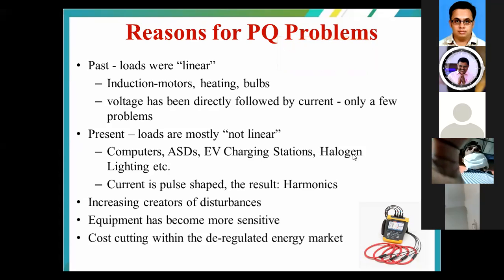That means in the sinusoidal wave, we are going to switch on or switch off the power electronic component at any instant. If the voltage is at the maximum point, that is at 90 degrees, and we are breaking the voltage at that particular point, the distortion is going to be larger, similar to that of the inrush current in the case of transformers. These are the creators of the disturbances, and equipment has become more sensitive, and because of this we are supposed to mitigate the power quality issues.